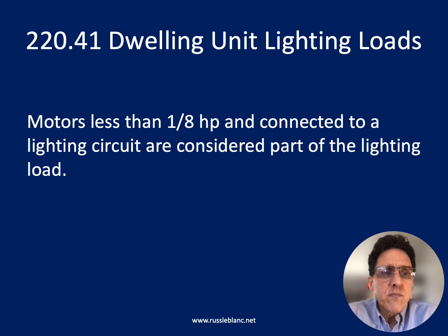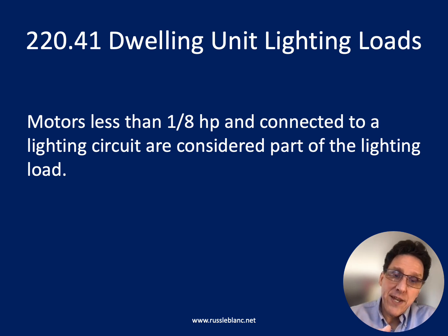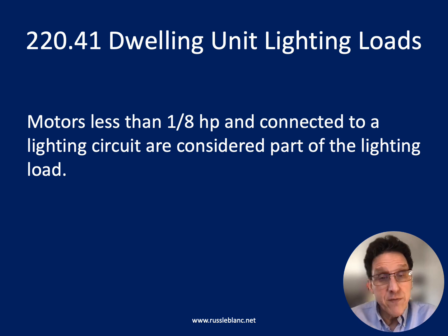Okay, small motors less than 1/8 of a horsepower and connected to a lighting circuit are considered part of the lighting load. No additional load calculations necessary. An example of that might be a paddle fan, right? A paddle fan in a bedroom is connected to the bedroom lighting circuit. No additional load calculation for that paddle fan, even though it is an appliance. It's just considered a lighting load in this case.